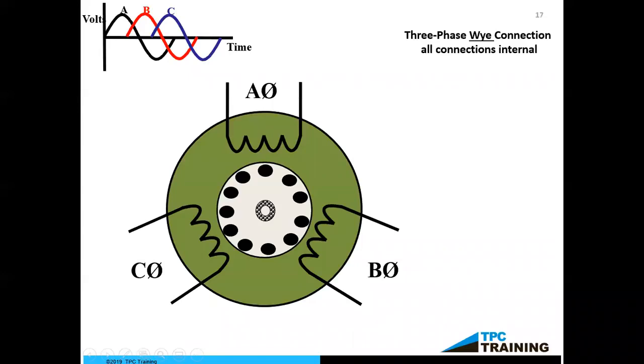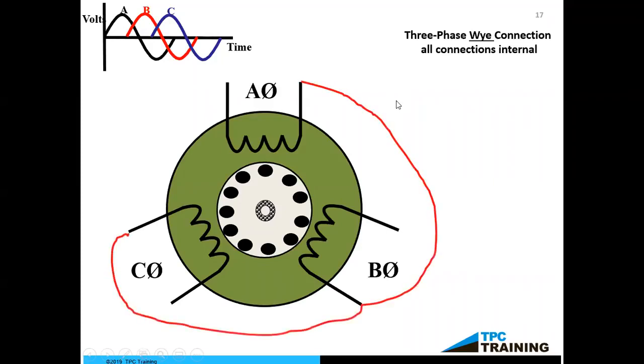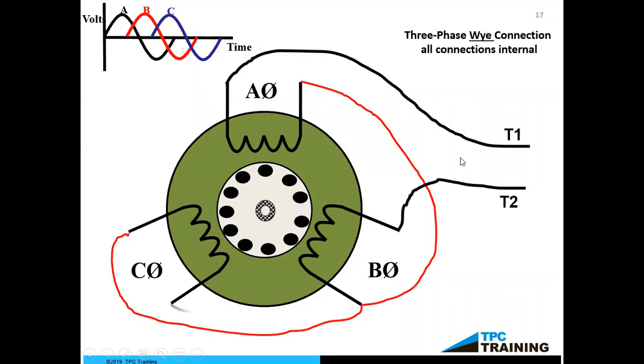So now we come to a little pictorial of that three-phase motor. And we can see that we have phase A, phase B, phase C, each one of these a solid winding, right? What happens with this is that we can connect it either in a Y or a delta configuration. This is going to be a Y configuration for us, and we're going to bring out first T1, then T2, and then T3.